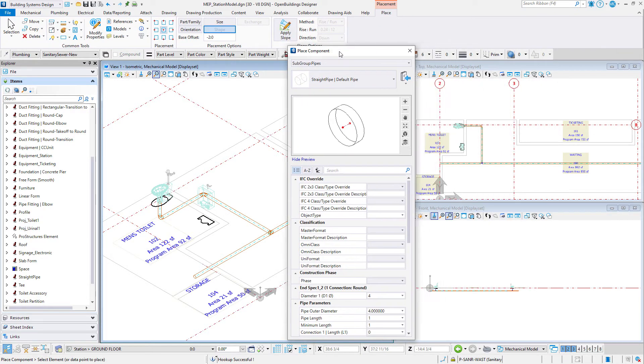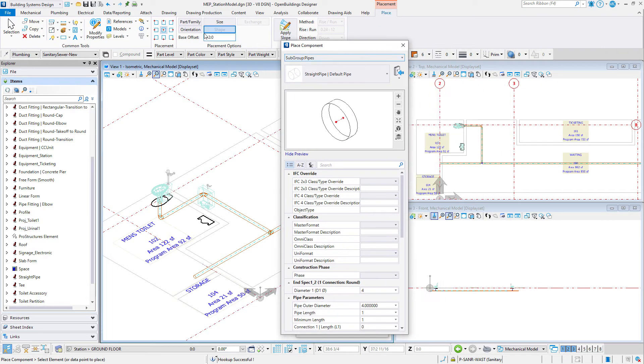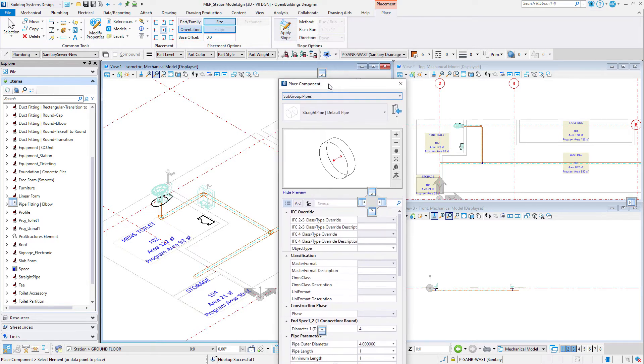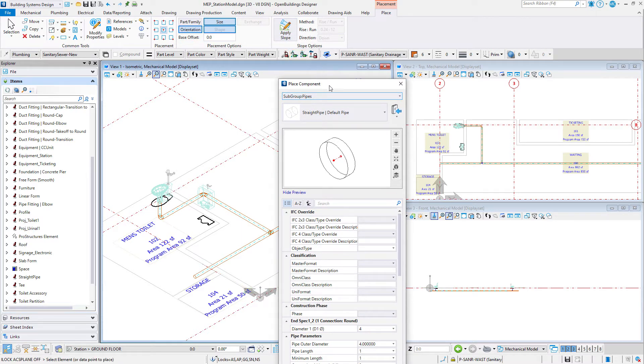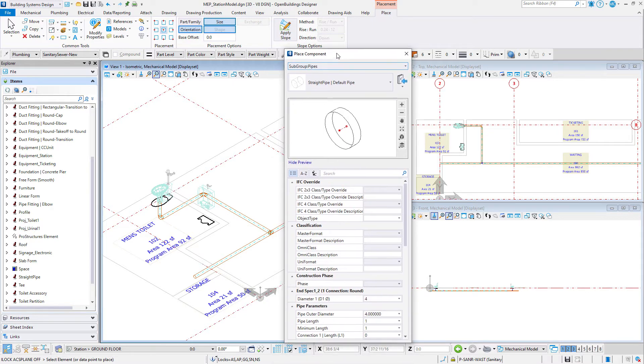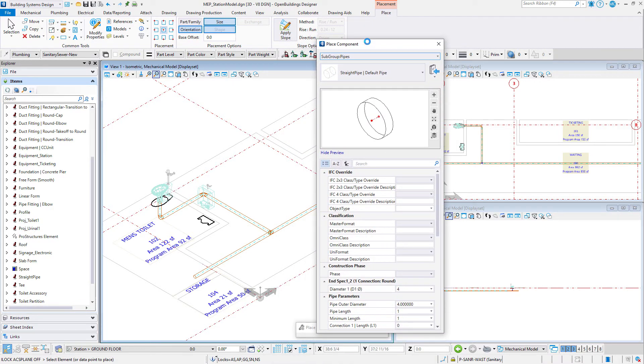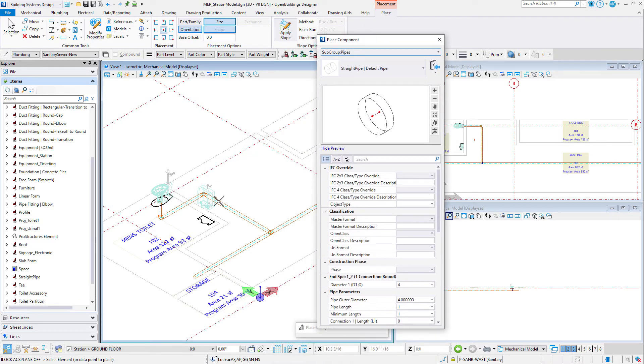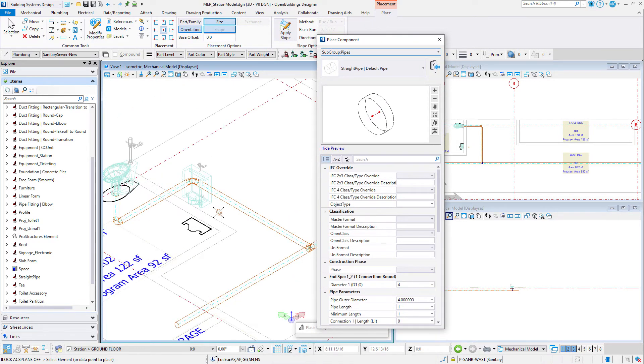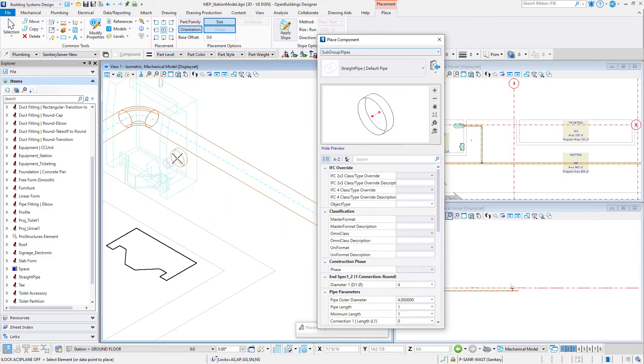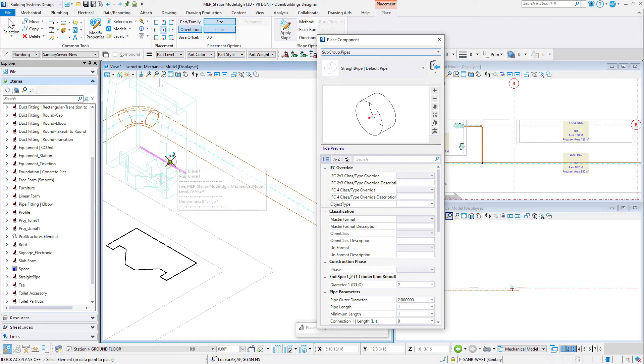On the placement ribbon, toggle on orientation and size, so the size and orientation of the pipe will be determined by the connection point on the fixture. Toggle off the ACS plane and ACS plane snap locks. Then snap to the sanitary connection point on the urinal and data point to accept. This will size the pipe and start the route.